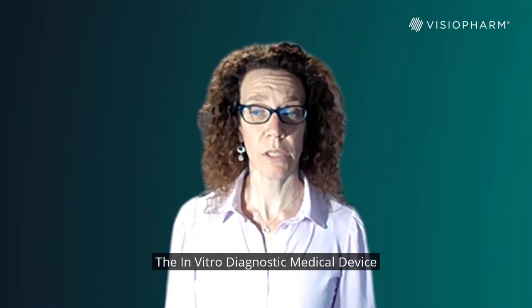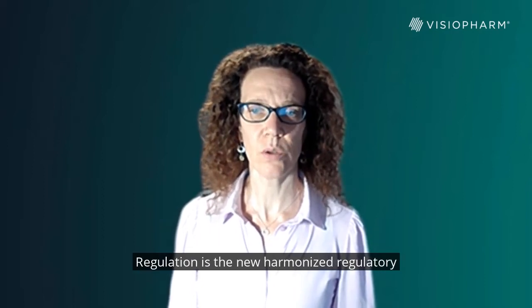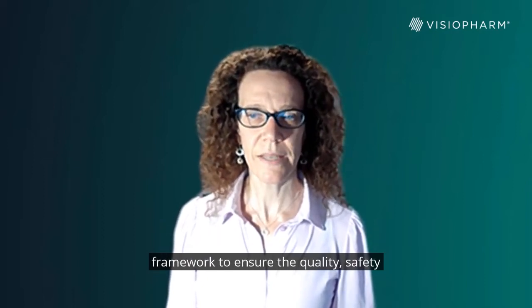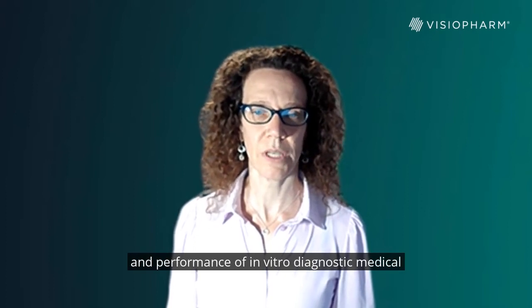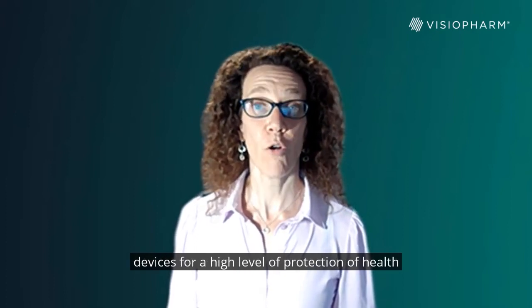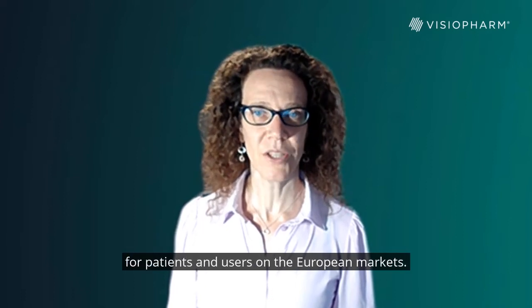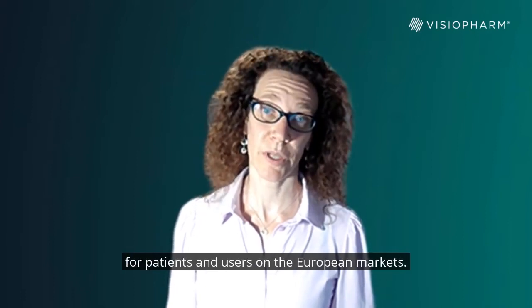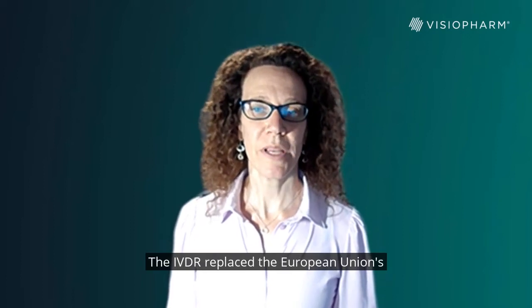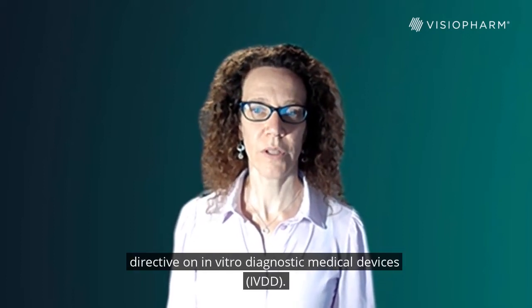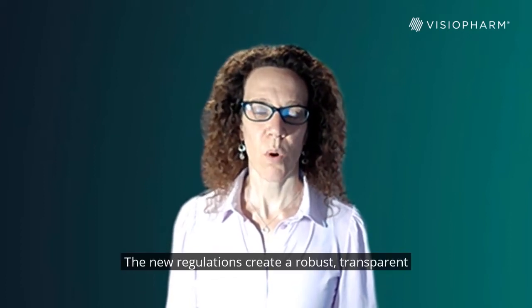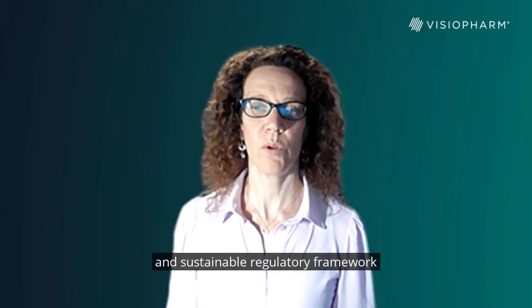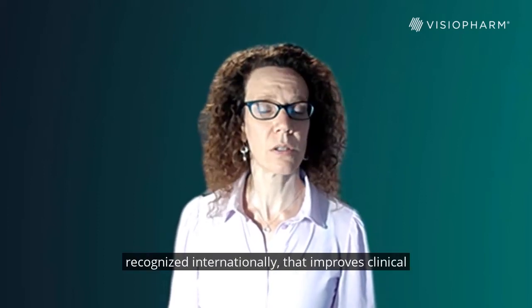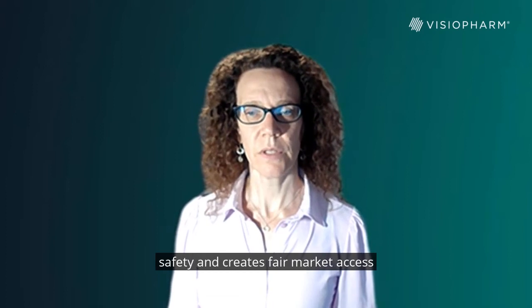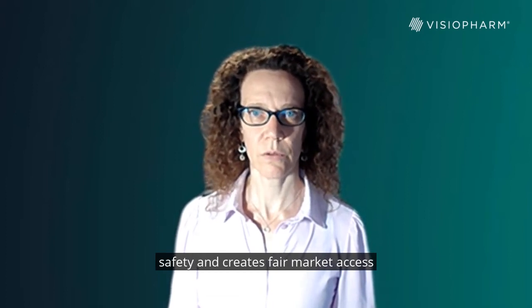The In Vitro Diagnostic Medical Device Regulation is the new harmonized regulatory framework to ensure the quality, safety, and performance of in vitro diagnostic medical devices for a high level of protection of health for patients and users on the European market. The IVDR replaced the European Union's directive on in vitro diagnostic medical devices, IVDD. The new regulations create a robust, transparent, and sustainable regulatory framework recognized internationally that improves clinical safety and creates fair market access for manufacturers.